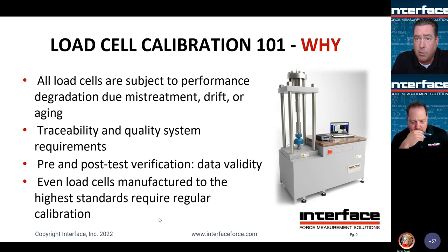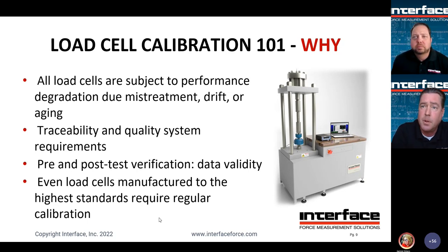And you are correct, we do trim some load cells. That is done as a step in the calibration process, and is more for if a customer desires to have a set or trimmed output. So we'd adjust it to a nominal sensitivity value. And that's typically done electrically, of course. Slide, please.